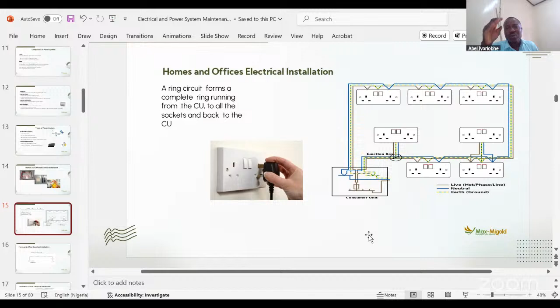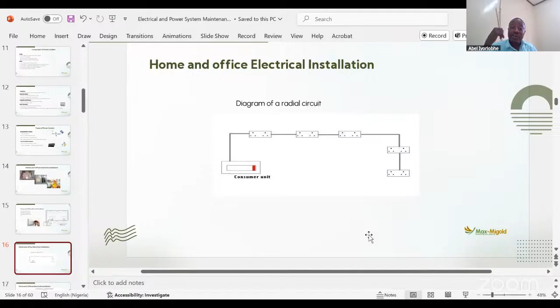So this is radial, from distribution board or consumer unit to where it is needed, like your AC. Never loop an AC switch; let it run from the distribution board to the AC point. The same with the microwave, or anything with a heating element - don't attach anything else to it. It should be standalone, because if you do, it will start tripping, and before you know it, it affects your circuit breaker. These are the ways you can reduce cost in your facility by paying attention to details.